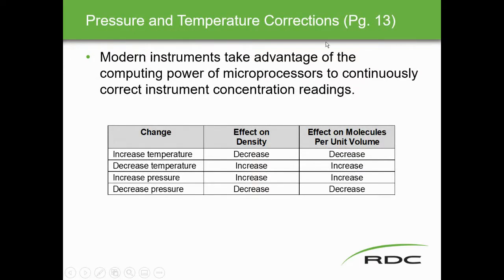Modern instruments use microprocessors to continuously correct for temperature and pressure. Increased temperature decreases gas density and the number of molecules, which affects the measurement. Temperature and pressure sensor readings are sent to the microprocessor to ensure accurate results.